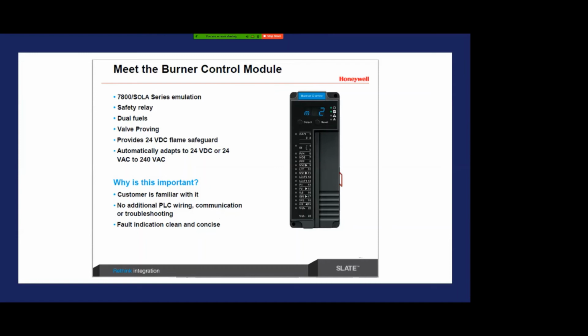So here it is, the burner control module. This module is 7800 and SOLA series emulation, meaning the functionality you can configure in this module can emulate both the 7800 and the SOLA series. It is the safety relay. It can handle dual fuels. Through this module we can provide VPS, valve proving, and 24-volt VDC flame safeguard, which is a unique feature. And again, it automatically adapts to that universal power we talked about.